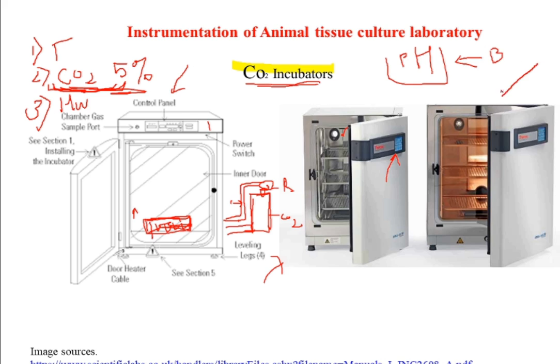This is a typical photo of a CO2 incubator, where you can see the shelf here, then a meter reading which provides the temperature. Outside also you will have digital meters which provide the temperature and the mechanism to set it. And nowadays we also have a light. One more glass shield is there, and here we put that autoclaved water to maintain the humidity, and from the back side we maintain the CO2.